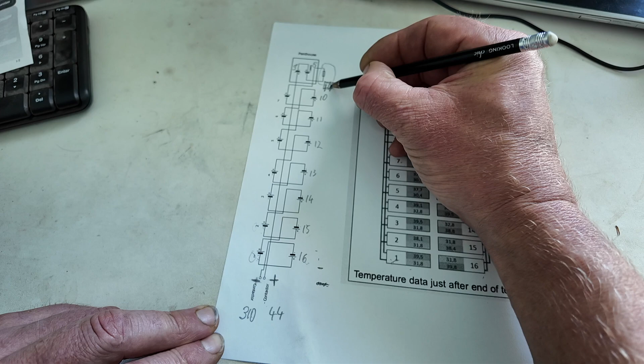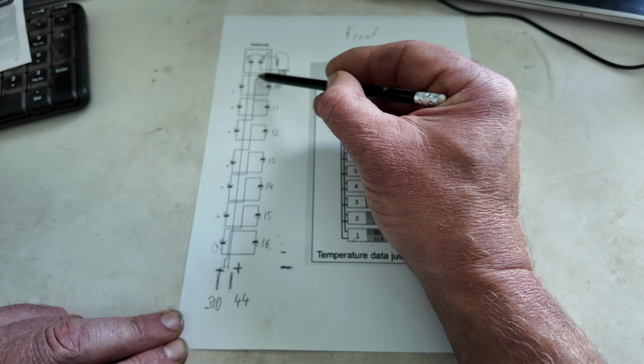If we do the same with the 310, divided by 22 is 14. So we count 14 modules and should again end up at the pyro fuse. It's pretty clear looking at the numbers already. So we start here: 1, 2, 3, 4, 5, 6, 7, 8, 9, 10, 11, 12, 13, 14, and boom, we are at the pyro fuse. That's how we can trace this back with a simple calculation.